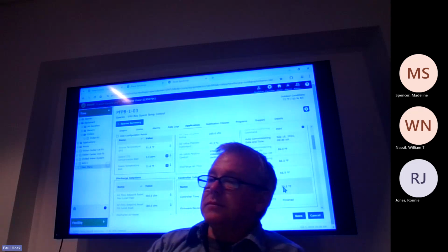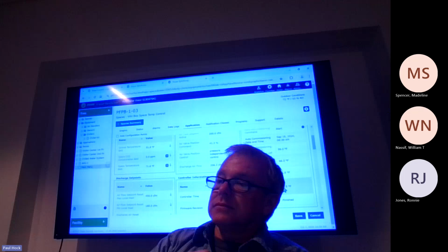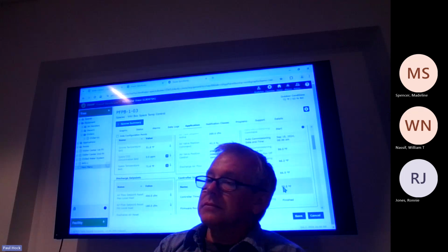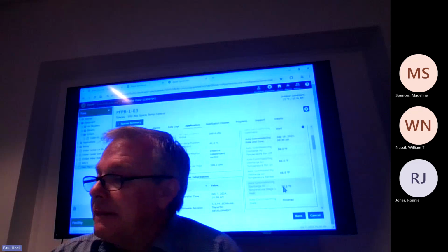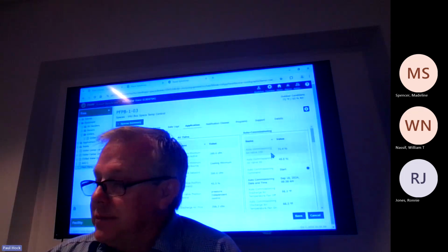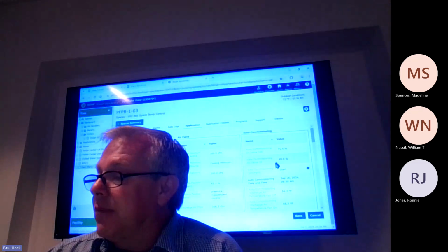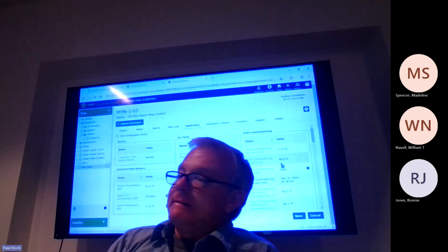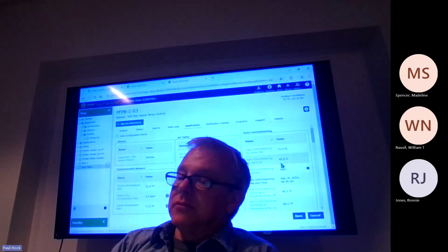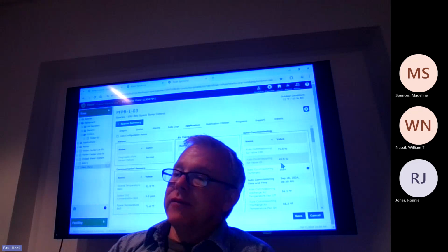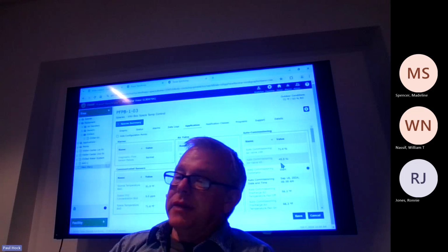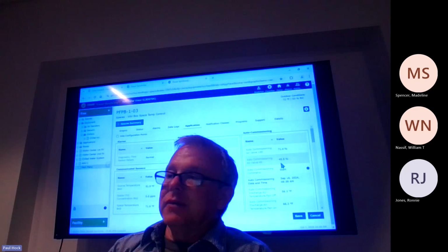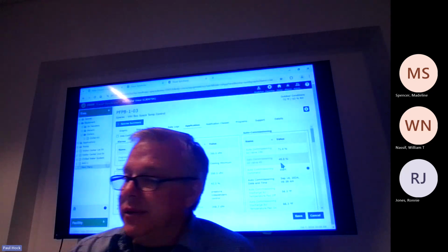So if you went in here and you recalibrated it and it came back and there was an issue, what would that look like? Or would it just tell you an alarm? It would tell you an alarm, but these would be 0. Okay. So it wouldn't just be under the 40, it'd be a 0. Yeah. So if it didn't make the airflow at 40% that it was looking for, or it didn't make its airflow at 100% set point, then it would just read 0. Okay. Then you would know there's an issue.